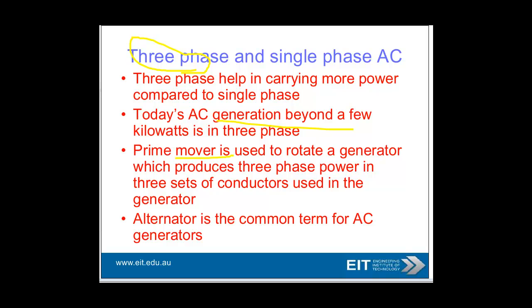So the idea is you have a prime mover, diesel engine, rotating generator, which produces three-phase power, 3 sets of conductors. Probably you could argue that if you've got 3 phases, you often have a star connection where you'll have a central neutral. Alternator is a common term used for AC generators.